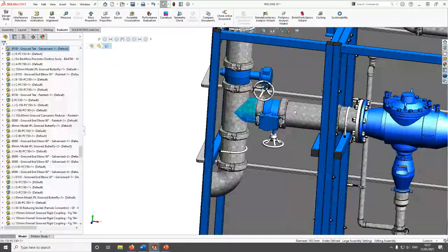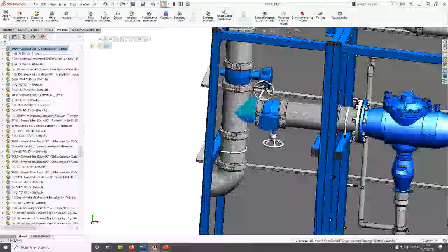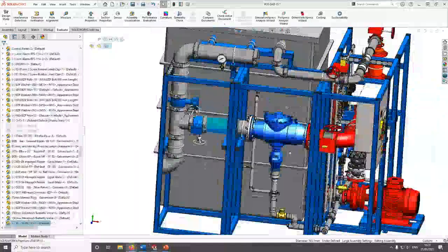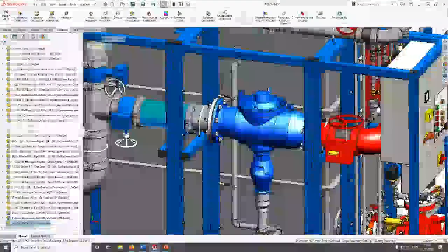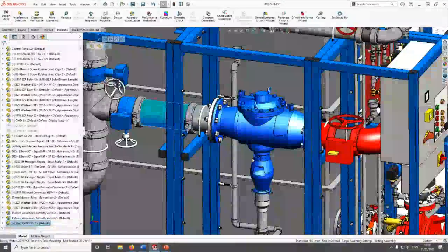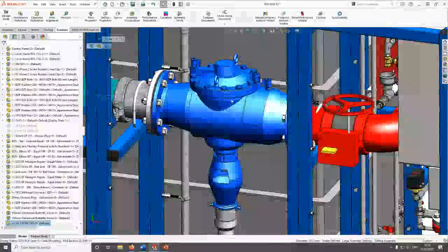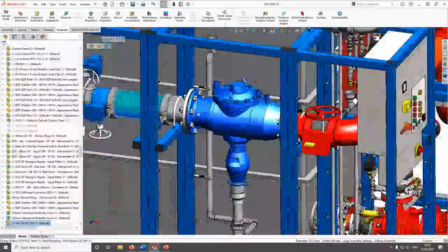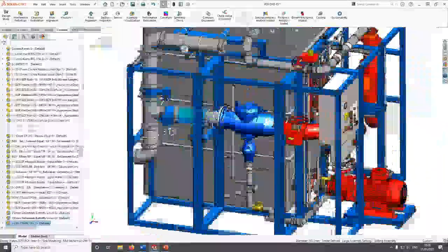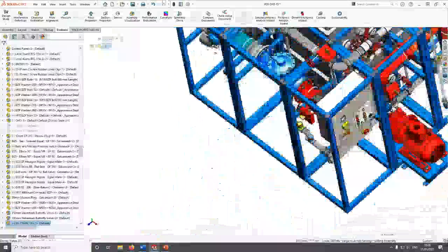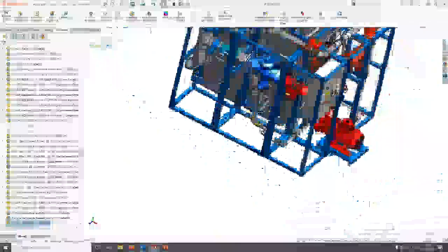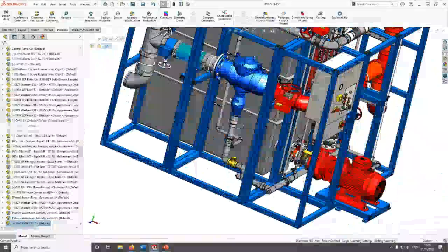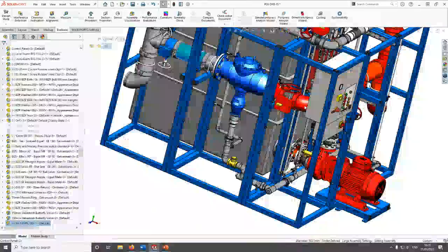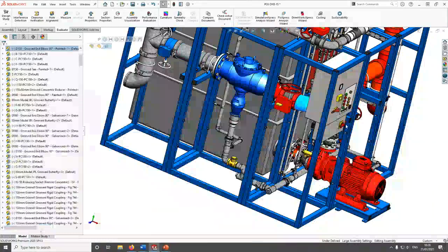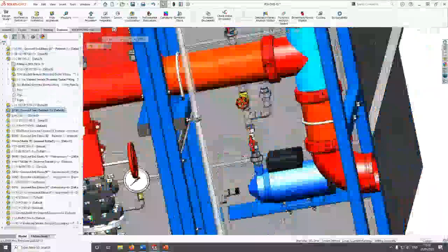So it's going to flow into this big blue unit here, which is called an RPZ, which stands for reduced pressure zone. It's like a super non-return valve. So again, WRAS approved components using the very best equipment for protecting town main. So that's going to go through this valve here, round the corner, and you can see that the pipework now switches to red rather than to blue or to galv, because now we're basically in sprinkler protection land. That's going to come around here, through here, and then out this side.